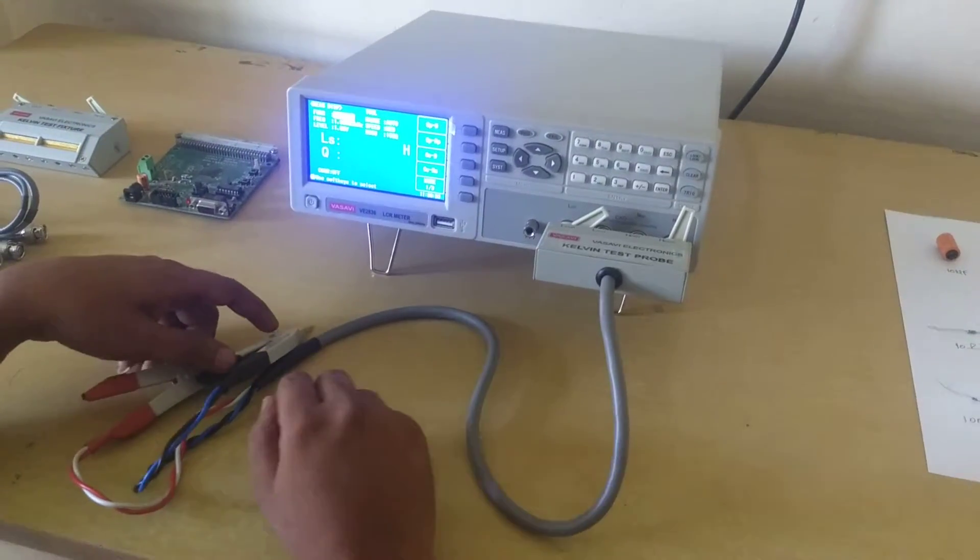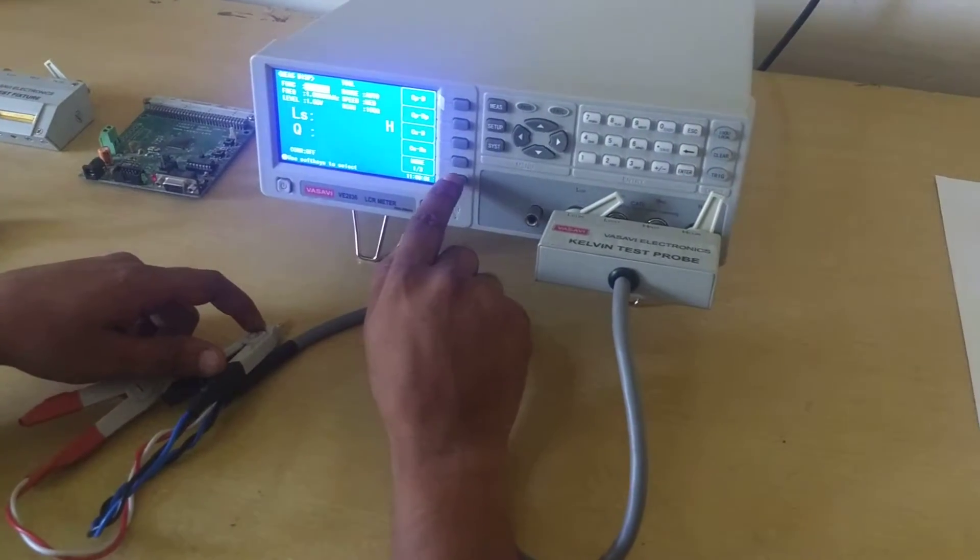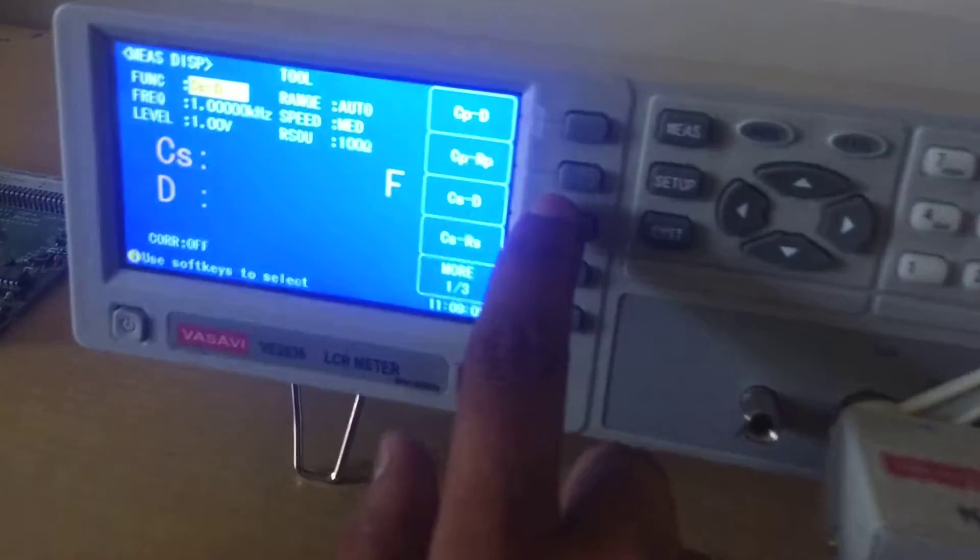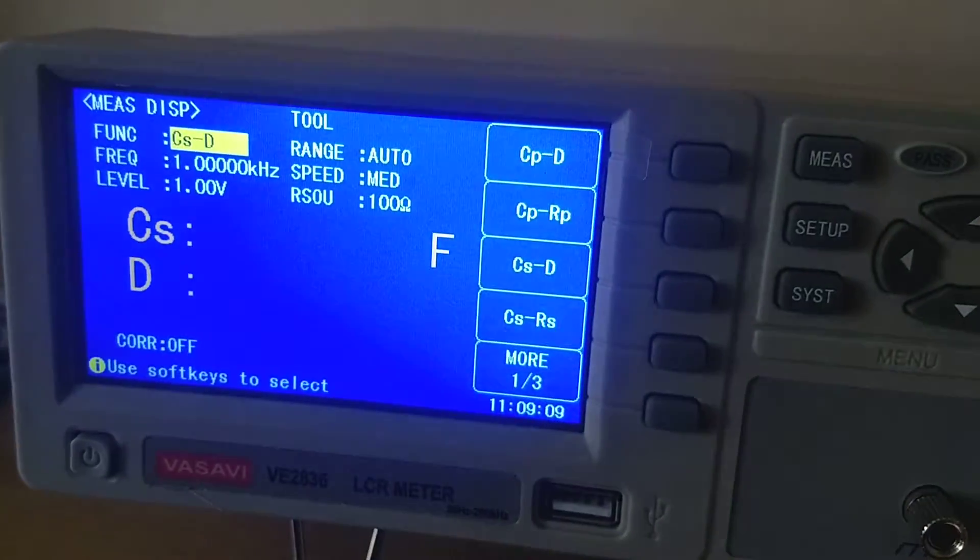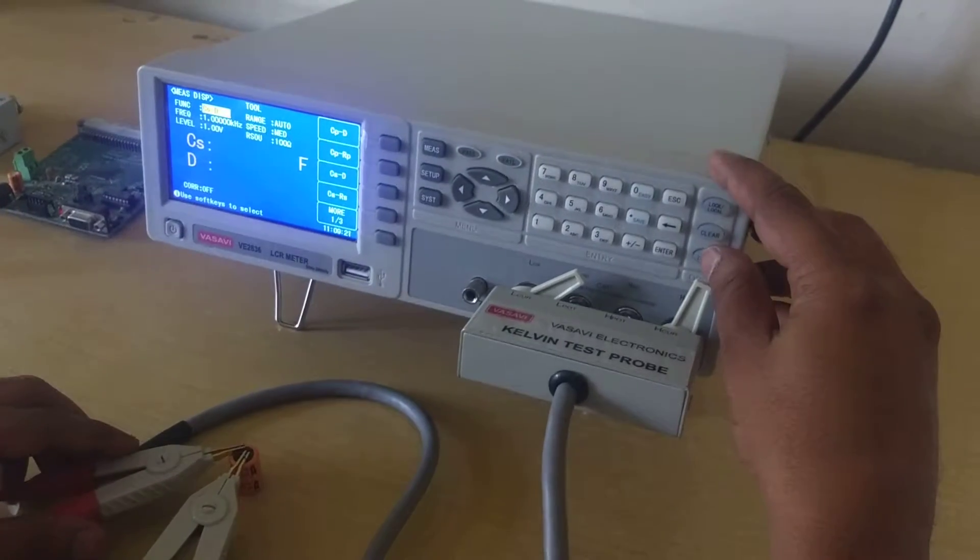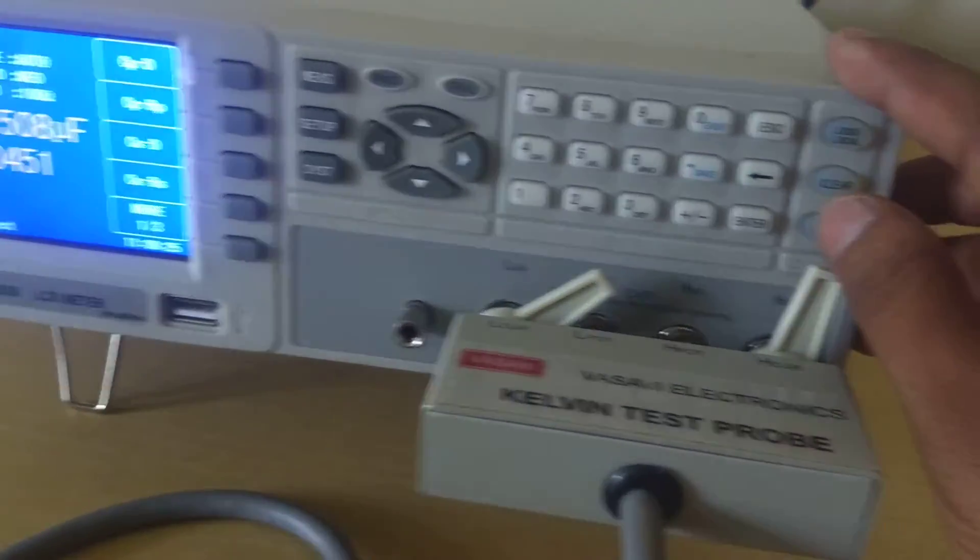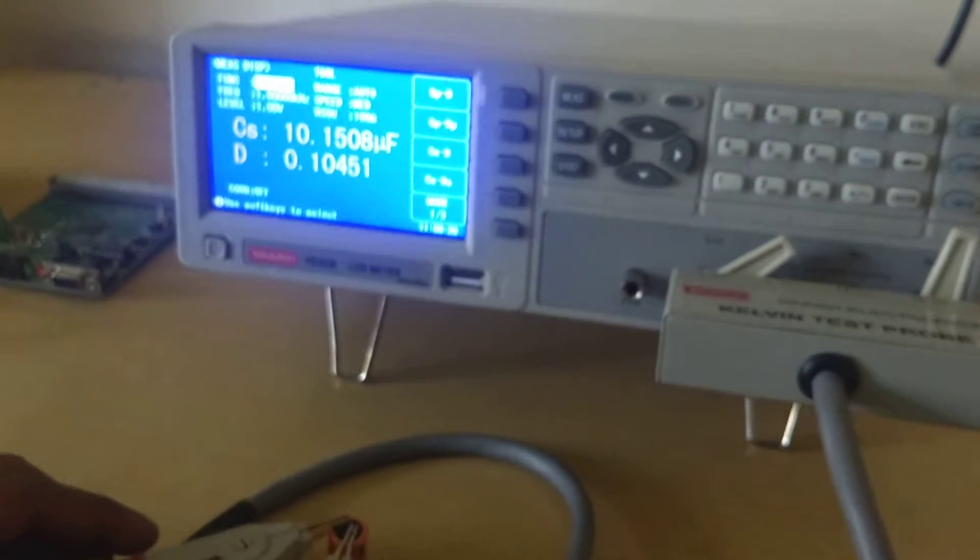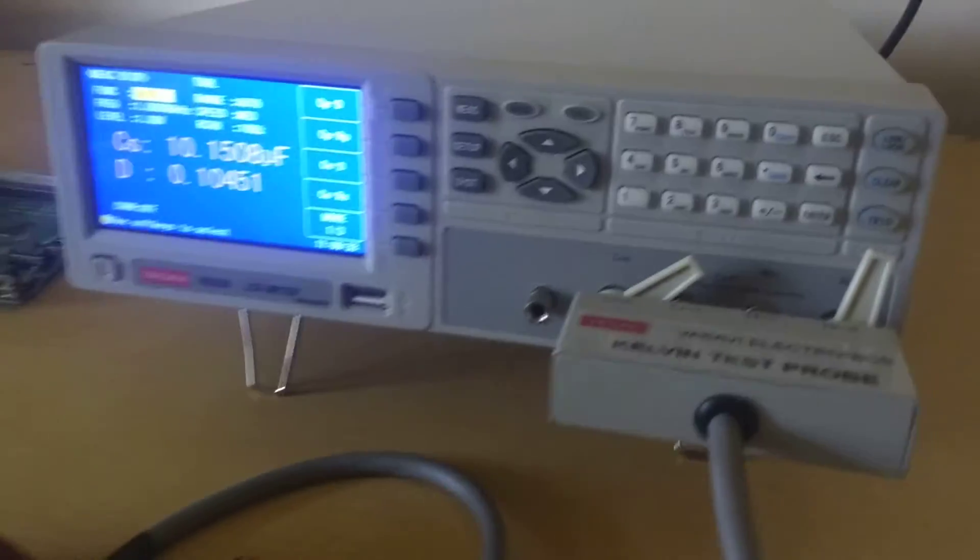Now I will show you how to test a component, a capacitor. First we will select the function. Since it is in trigger mode, we need to press trigger for the reading. In trigger mode, we have three modes: internal, external, and manual.